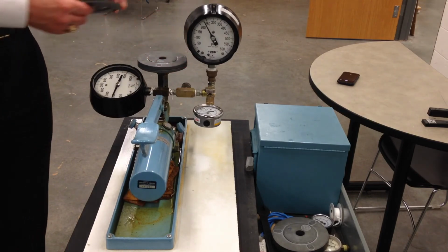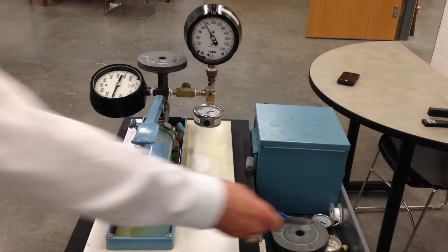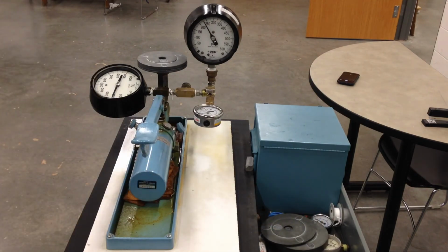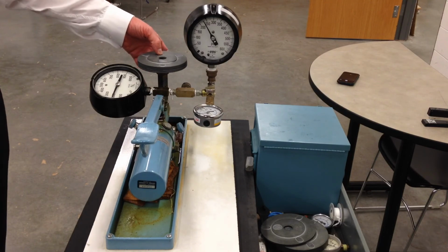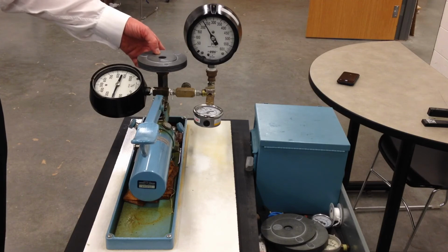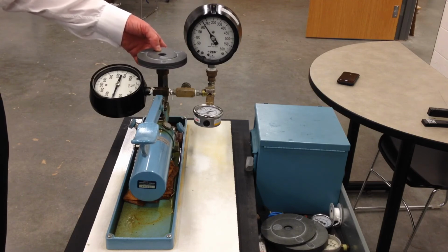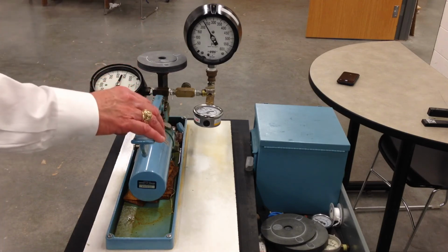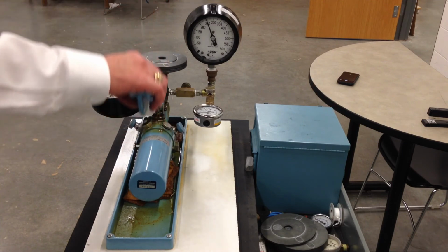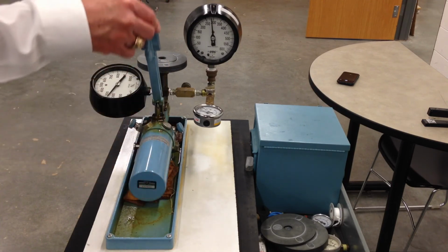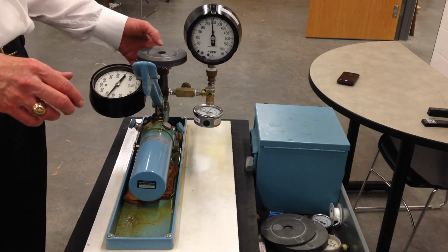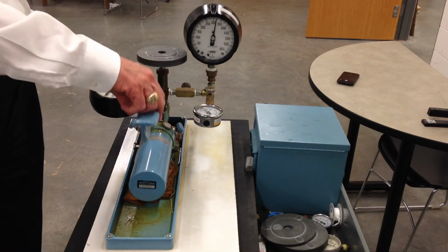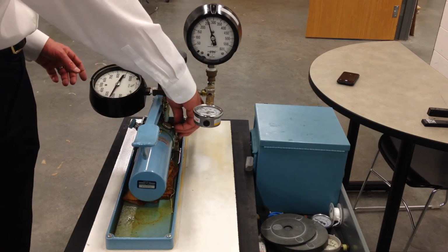Now you will notice that the piston drops to the bottom. And so therefore, what I want to do is have this thing float. I want this thing to be in static equilibrium between the weights on the top and the pressure at the bottom. So I'm going to go ahead and start pumping. And I notice that the gauge increases. Oops, I've overdone it. See, now I'm at the top and it goes up. So what I have to do is release it.